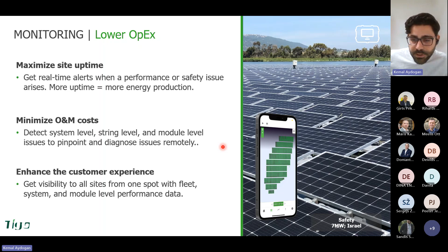Let's go here. For example, this is an Italian site. Without module level monitoring, you wouldn't know which PV modules are working less and why. You would have to go to the site with your technician, and your technician would have to check each PV module, each cable, and spend more time there to understand what the problem is. This is the reason why module level monitoring is actually increasing the savings, because it decreases the operation and maintenance costs.